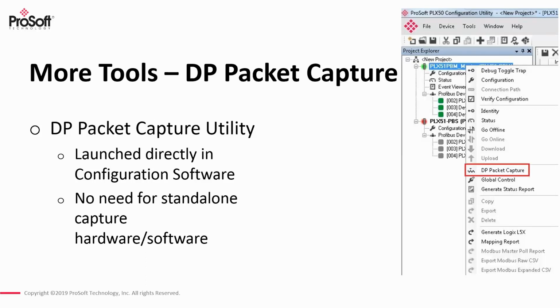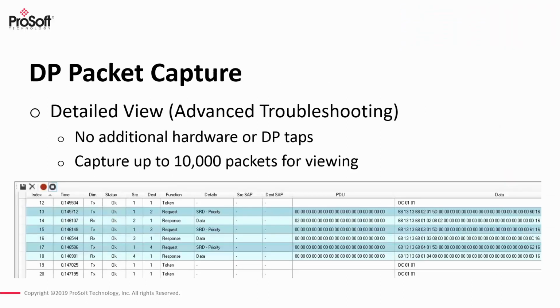With this DP packet capture utility, this is provided in the PLX50 configuration software. So it will allow you to basically launch a packet capture directly from the software without any other standalone hardware. And then it gives you a detailed view for advanced troubleshooting of all the PROFIBUS DP communications on the network. And so you can capture up to a total of 10,000 packets for viewing. And this tells you the advanced PROFIBUS DP.